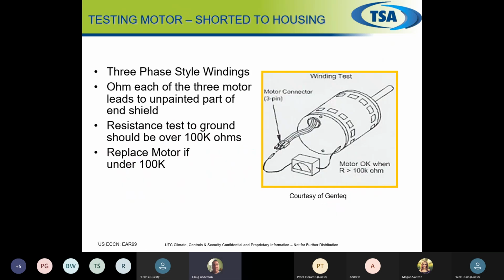So we're going to check the windings on the motor. We're just going to do a winding test to each part of that motor. We're just going to go ground to each side. We should have 100K ohms on each one. Replace the motor if you're under 100K ohms. Pretty simple.